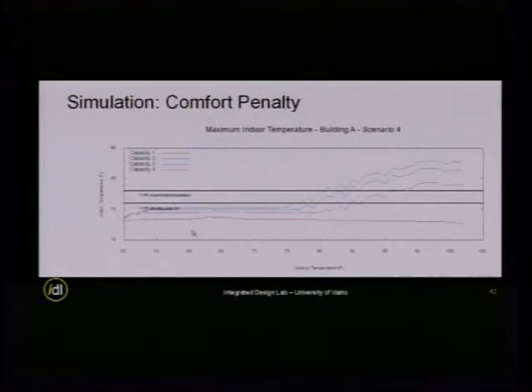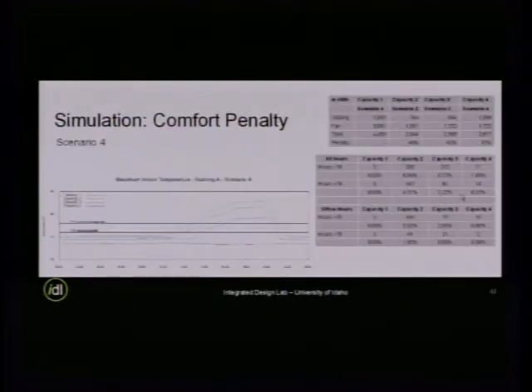This is another way to present it. This is the indoor temperature and this is the outdoor temperature, on scenario 4. On scenario 4 and capacity 4, you will be fine as long as the outdoor temperature is less than 93. So you want to have big meetings? Listen to your weatherman. It's going to be hard. Okay, make it in the morning. That's a big meeting, 20 people in the room. Will they take the risk for that? Maybe we can quantify that.